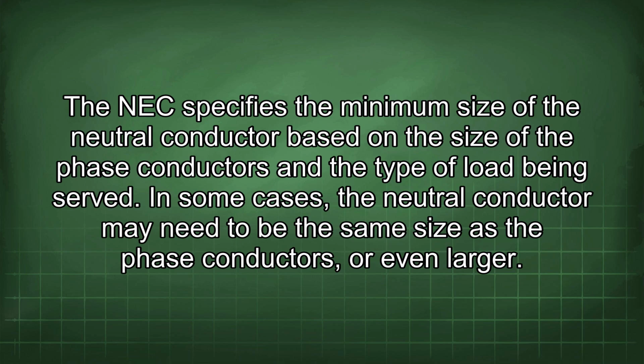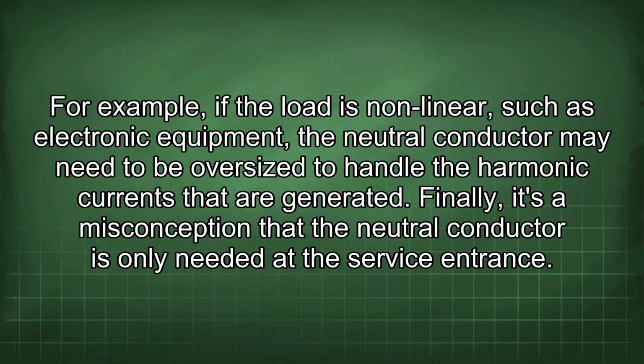The NEC specifies the minimum size of the neutral conductor based on the size of the phase conductors and the type of load being served. In some cases, the neutral conductor may need to be the same size as the phase conductors or even larger. For example, if the load is nonlinear, such as electronic equipment, the neutral conductor may need to be oversized to handle the harmonic currents that are generated.